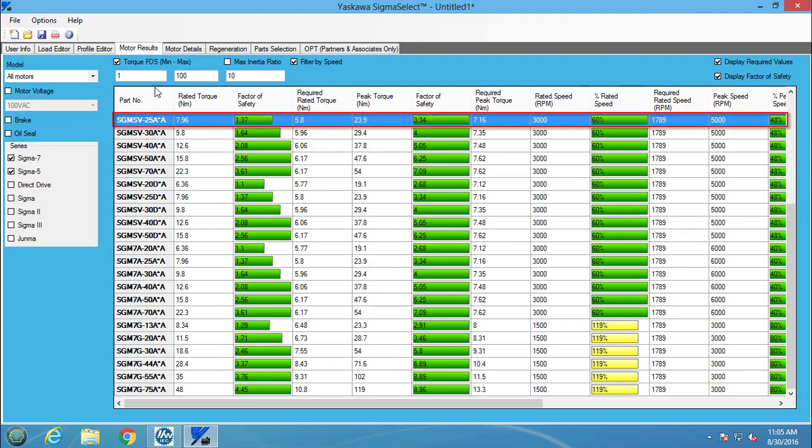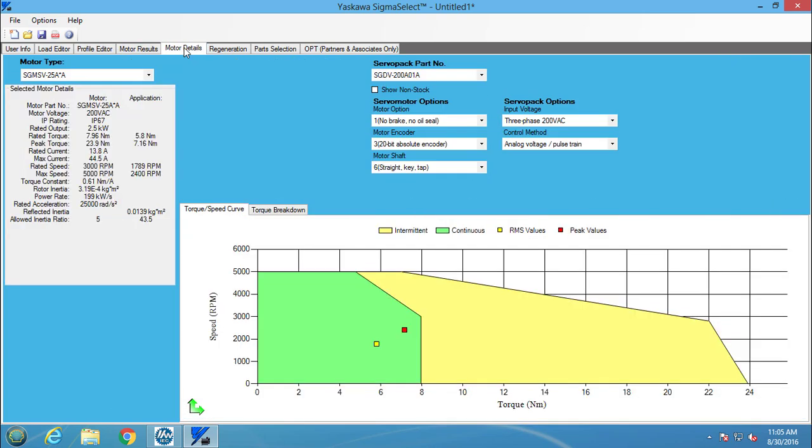I am going to select the SGM-SV-25A motor and move to the Motor Detail tab. The torque and speed curve shows me that the RMS and peak values both lie within the motor's capacity, so the motor will work for the application.